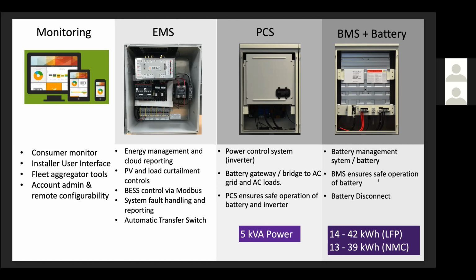The BMS ensures a safe operation of the battery by monitoring voltage, temperature, and other battery health metrics, and communicates that back to the inverter for charge and discharge ratings. Also housed within the DC cabinet is the battery disconnect. It's basically a DC breaker, a kill switch inside here. For the LFP system, the capacity ranges from the 14 kWh base system up to 42 kWh maximum, and the NMC or ESS version of the Evolve product is scalable from the base size of 13 kWh up to 39 kWh.